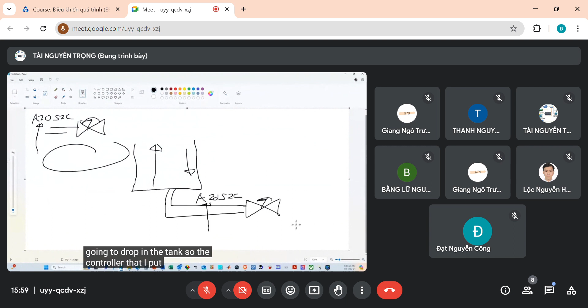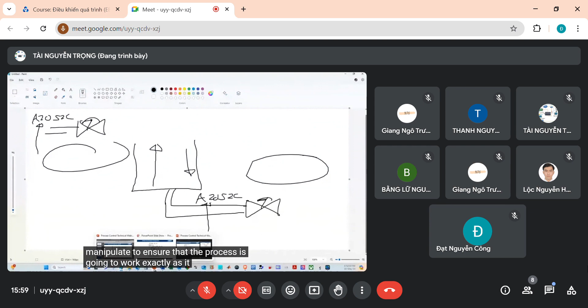What are the basic final control elements in a refinery plant? Shadrach, how about something like a control valve or an actuator connected to it? Or a variable speed drive connected to my pump? Those are examples of final control elements. The final control element is whatever I manipulate to ensure the process works exactly as it needs to.